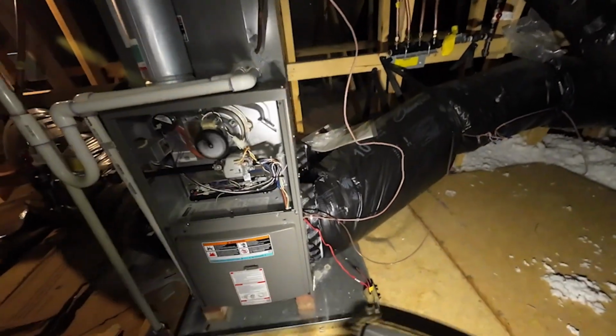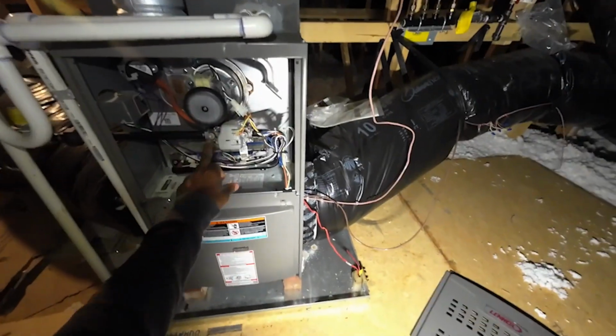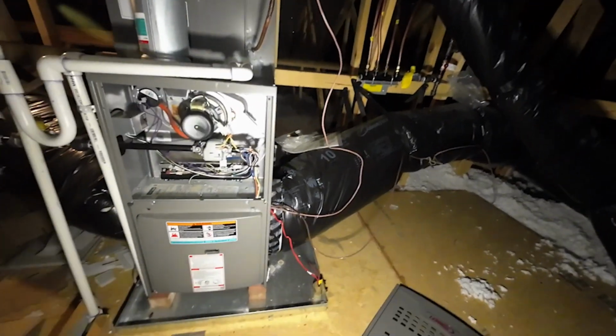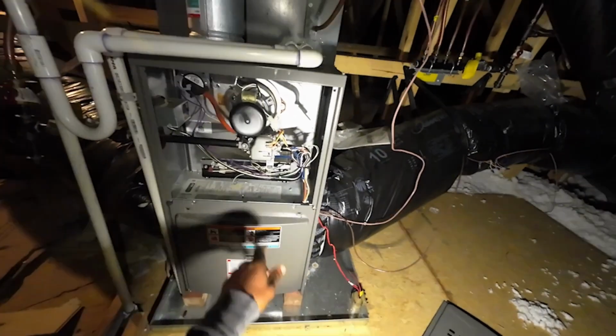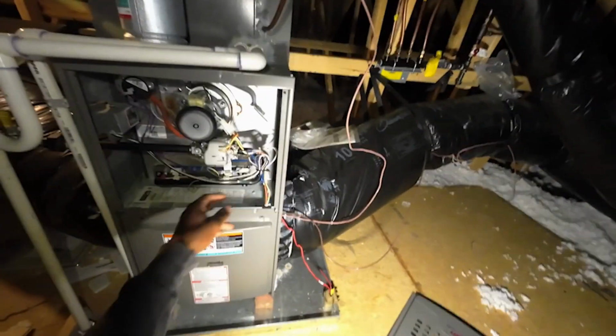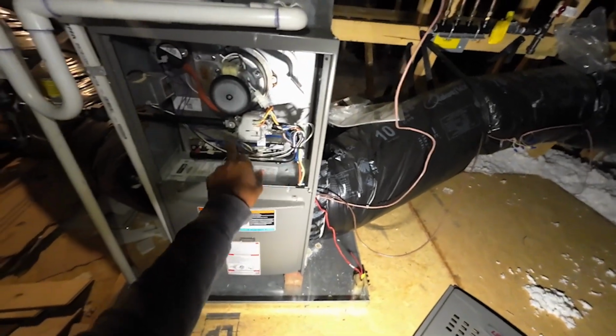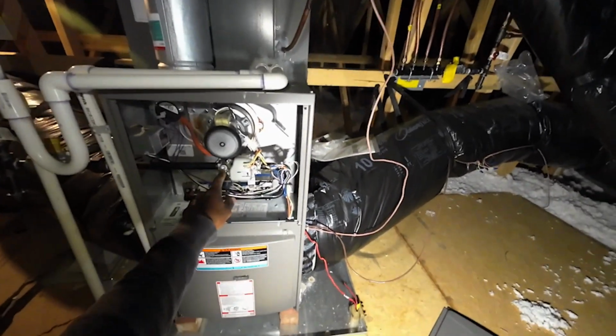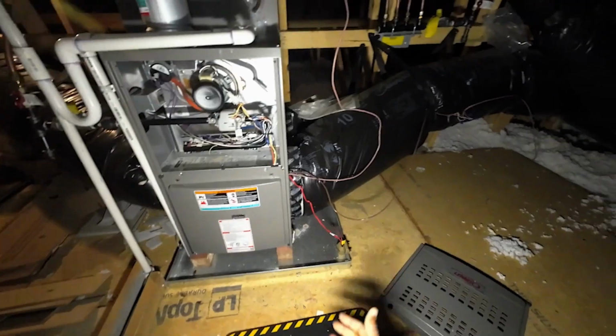Yeah, exactly. This is one of the gas valves. Remember I told you, hey, 70% of the time you can check the gas with the system running? This is the one where you can't. Well, you can, but it's more dangerous. So you've got these type of screws in here. You have to take those out, and it lets a lot of gas out compared to the other style.